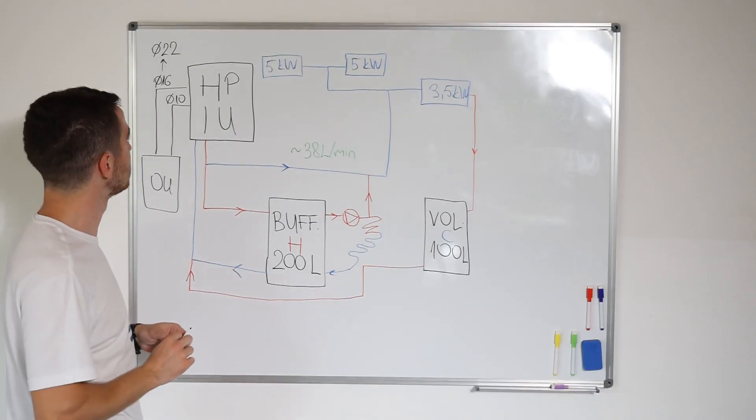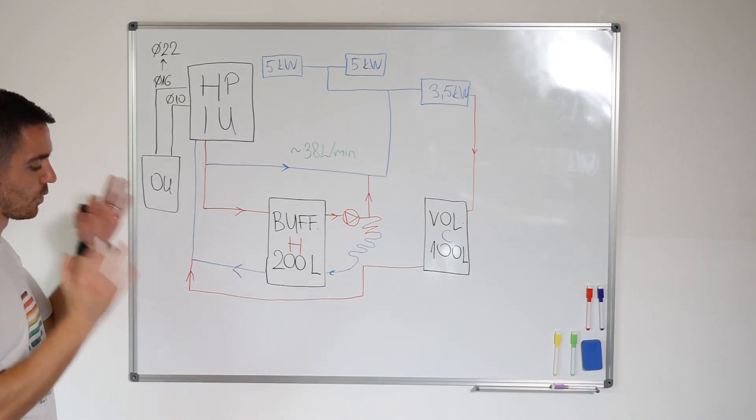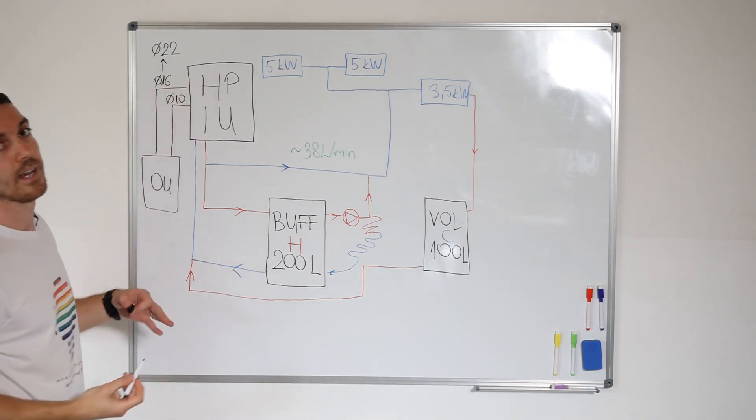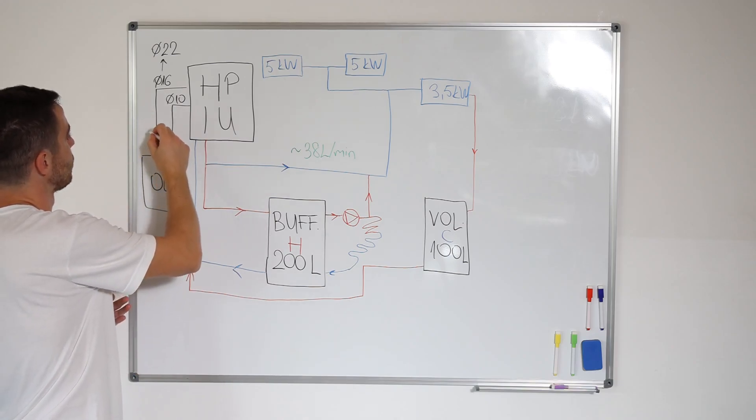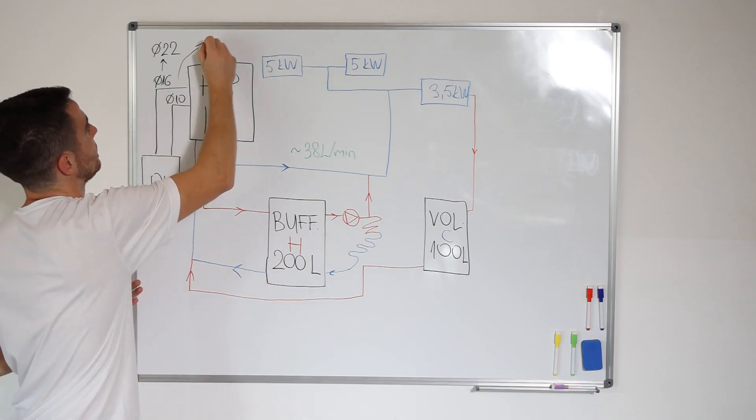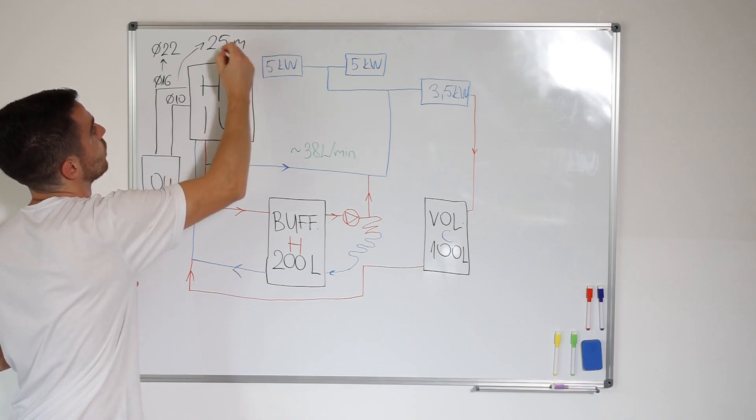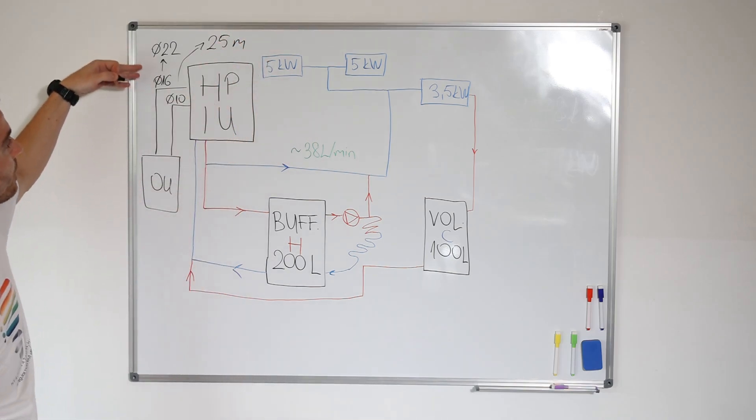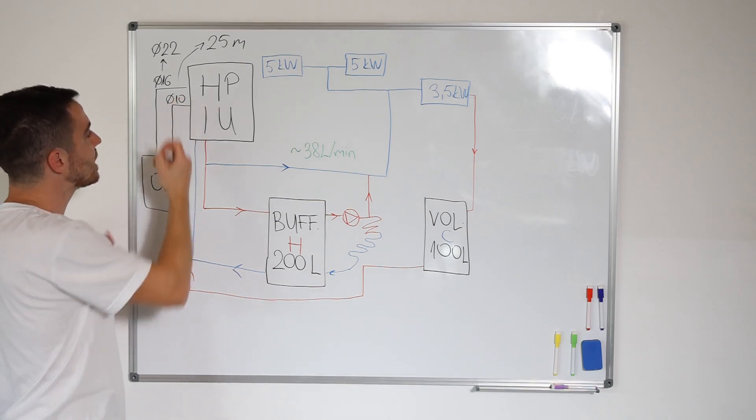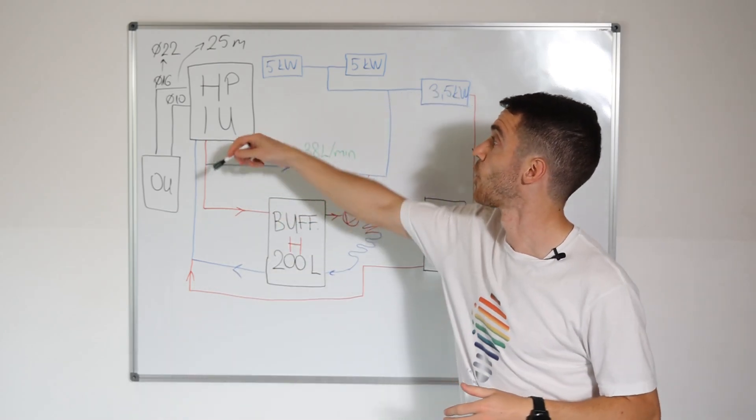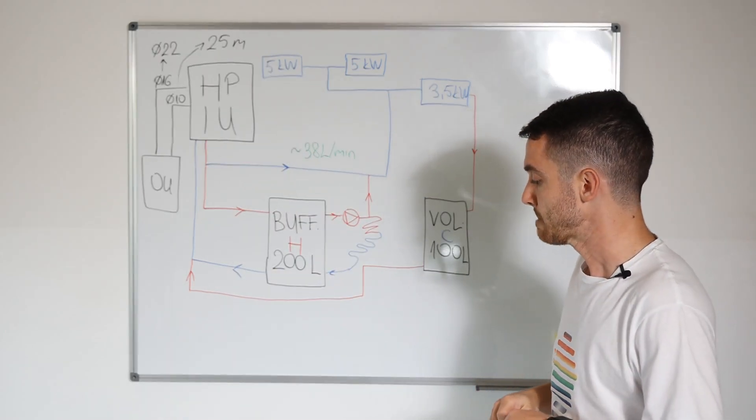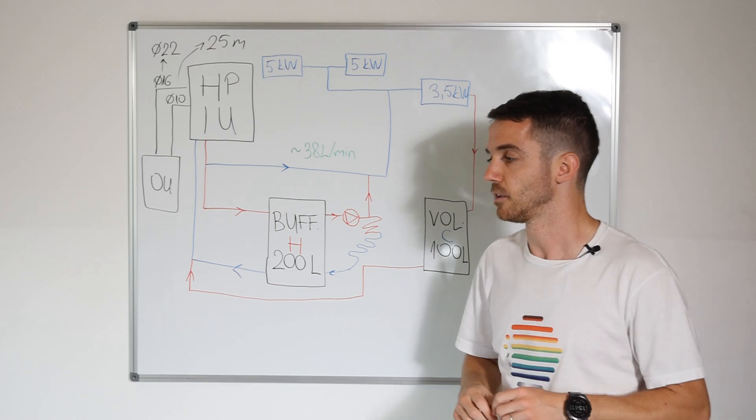We'll try to explain refrigerant technology in the future. But for now, you need to add additional refrigerant. And also because installation was, I think, 25 meter. So for 25 meter, you have gas pipe way bigger than must be. And liquid pipe is fine. After startup, no one realized that wrong pipe is here and they started doing it in cooling.